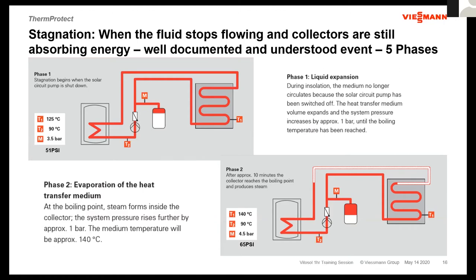Oftentimes, if you have a solar thermal system in your home, it's probably gone into some sort of stagnation. Maybe you went on holidays. Maybe the pump failed one day. Maybe a sensor went bad. Maybe you had a power outage. Nothing worked, and you didn't think about it. You went out shopping that day and your collectors are sitting up there on the roof. And all of a sudden they hit the stagnation and all this stuff was happening.